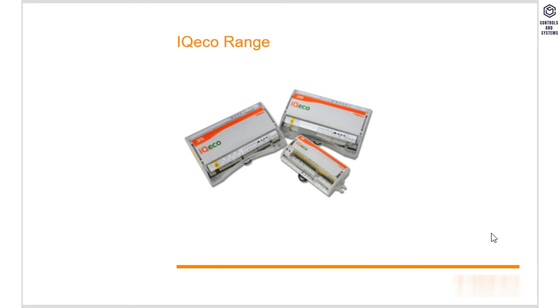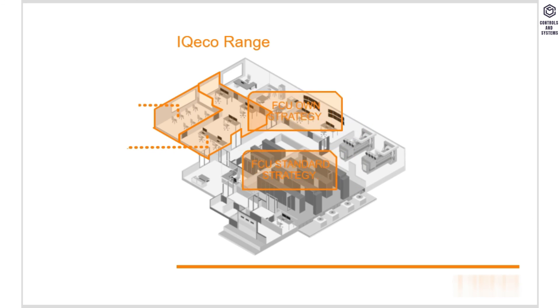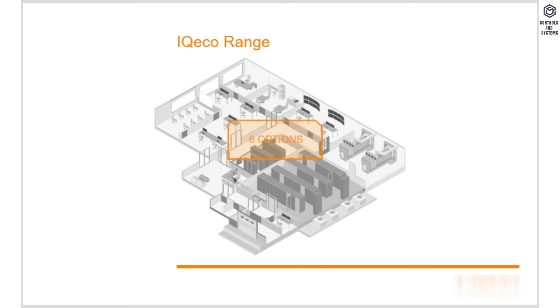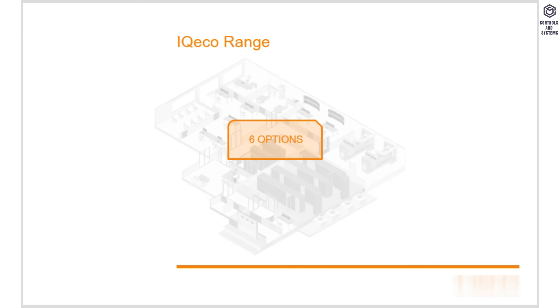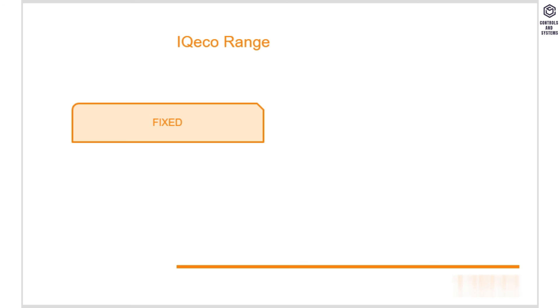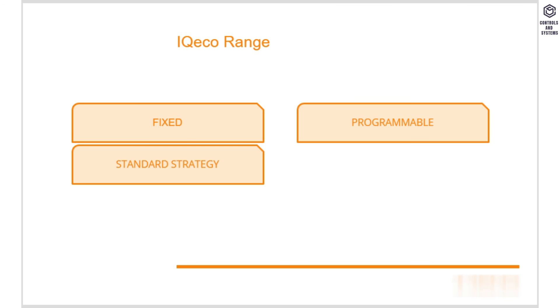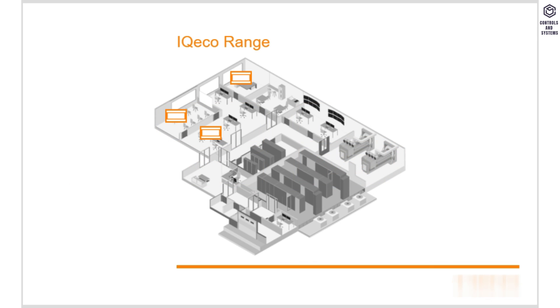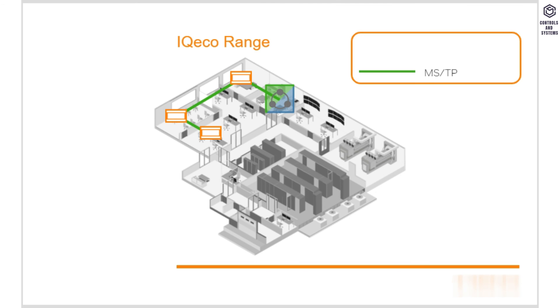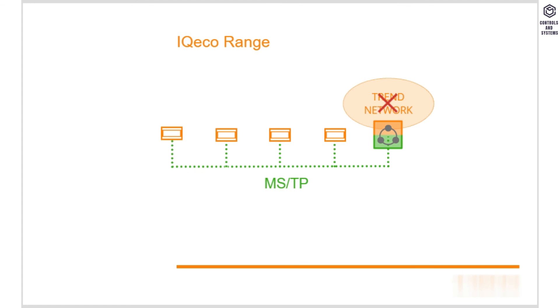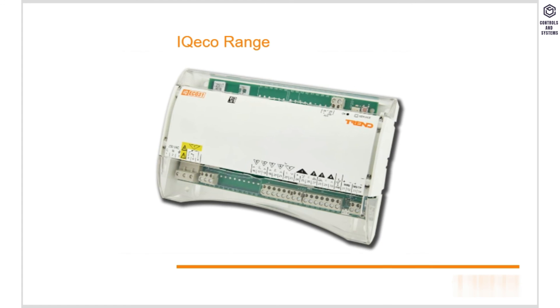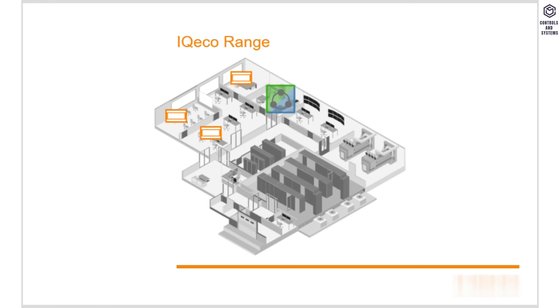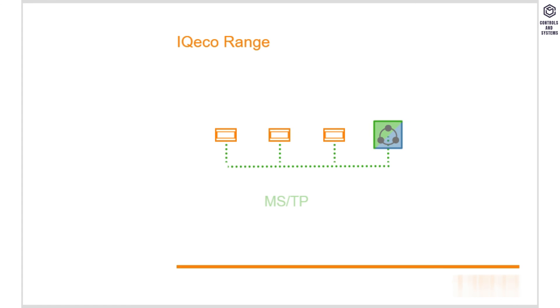The IQeco are application-specific controllers with between 10 to 18 input-output channels. The range consists of six options. Each is available as a fixed function variant which has a library of predefined strategies matching many roles that an IQeco may be suitable for. There is also a programmable variant which allows you the use of the library or your own targeted strategies. They communicate with other IQeco devices on the BACnet MSTP network and with other Trend network devices by way of an IQ4NC. If your IQeco devices are not connected to Trend devices, then a micro USB port is available providing direct local interfacing from a PC. IQeco controllers can also utilize BACnet over MSTP to speak to non-Trend devices that sit on the same network.